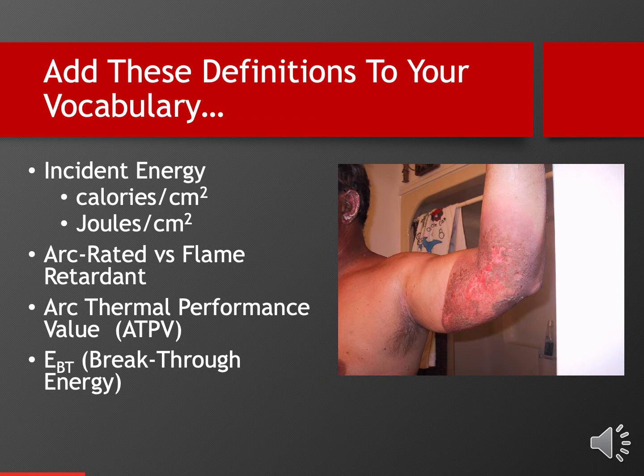Arc rated versus flame retardant or flame resistant. Arc rated has two primary differences between flame retardant or flame resistant clothing. One of them is the way it's tested. An arc-rated outfit is tested when exposed to an electrical arc, which has a different kind of heat gradient to it than, say, a fireman running into a burning building. And it also includes something that you see on the bottom, that E sub BT, which is called breakthrough energy. That's the blast part of the discussion.